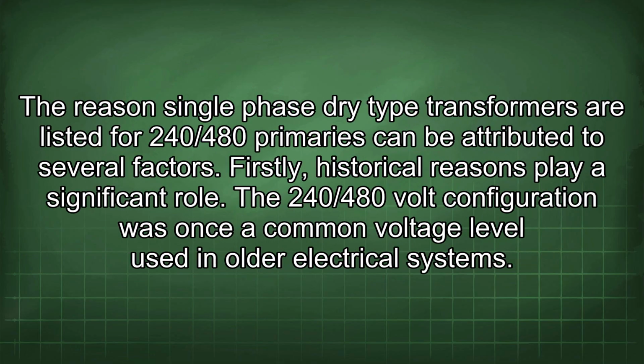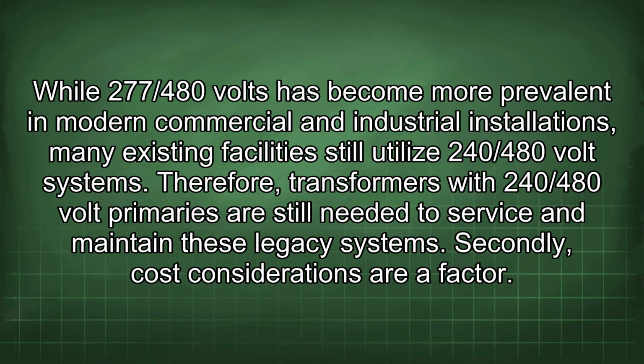The reason single-phase dry-type transformers are listed for 240/480 primaries can be attributed to several factors. Firstly, historical reasons play a significant role. The 240/480 volt configuration was once a common voltage level used in older electrical systems. While 277/480 volts has become more prevalent in modern commercial and industrial installations, many existing facilities still utilize 240/480 volt systems. Therefore, transformers with 240/480 volt primaries are still needed to service and maintain these legacy systems.